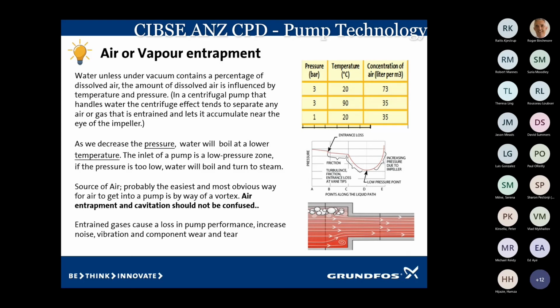And that air circulates around, it accumulates to the point where it can actually airlock, and you won't get heat into the radiators, you won't get heat out, it will airlock the pipework, and eventually it'll get into the pump at the same time. So as we decrease pressure, the air will come out. If we increase the temperature at the same time and we don't have enough pressure on the system, then we'll get that air out of there as well.